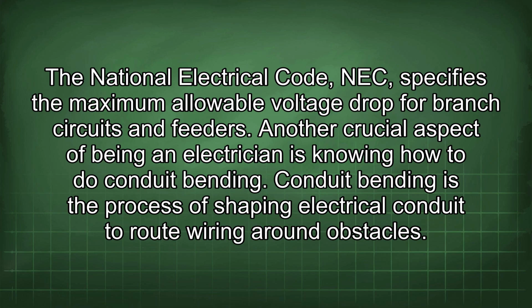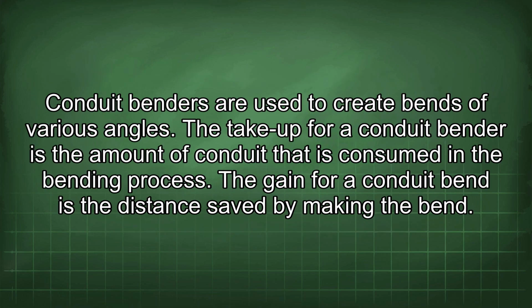Another crucial aspect of being an electrician is knowing how to do conduit bending. Conduit bending is the process of shaping electrical conduit to route wiring around obstacles. Conduit benders are used to create bends of various angles. The take-up for a conduit bender is the amount of conduit that is consumed in the bending process. The gain for a conduit bend is the distance saved by making the bend.